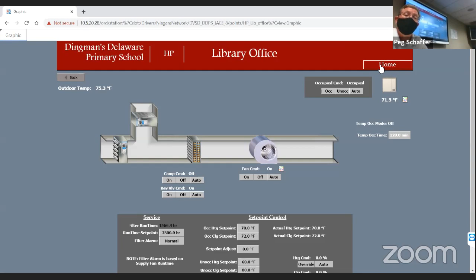Heat pumps are very much like a univentilator. If you walked into Dingman's Primary School and looked at the univentilator, you'd say that's the same thing they have at the high school — and it is. The box looks the same, but the mechanical workings are completely different. They're not even close; they work in totally different ways. The ventilation side is very equal — air comes in fresh, mixes with the return, and blasts back into the room. So the ventilation side is equal, but the heating and cooling are totally different. We don't need to get into all the details of how that functions, but just understand there are many different types of systems throughout your district — heat pump, HP, on the cross-reference sheet Marvin provided.